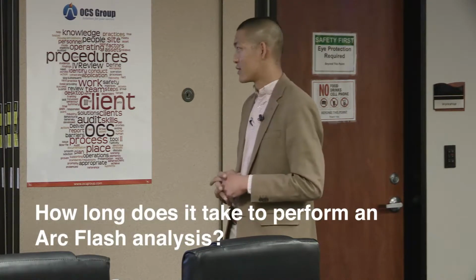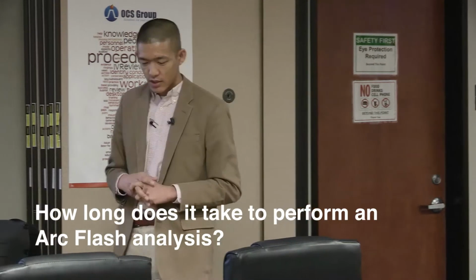And then for those that are interested in how long it takes to perform an arc flash study, once we have all of the information of the system, generators, motors, and this is all nameplate data, cables, transformers, once we have all that data entered in, it typically takes another 2 to 3 weeks to finalize the studies. But the largest amount of time is spent in modeling the system and making sure that you have all the details correct.